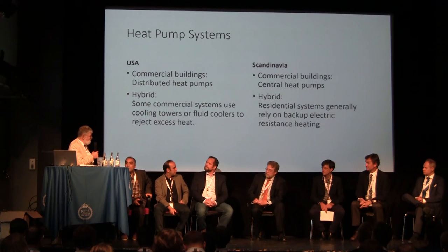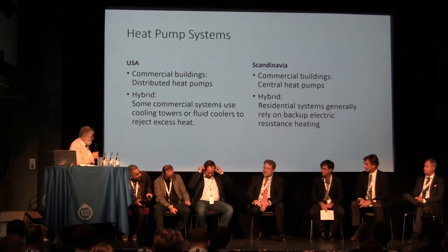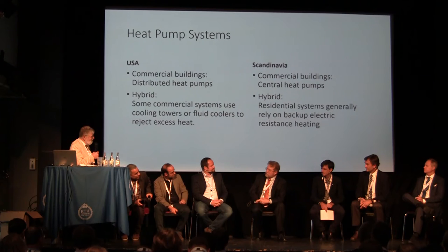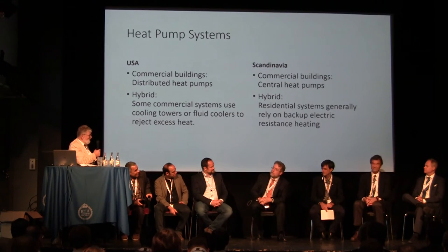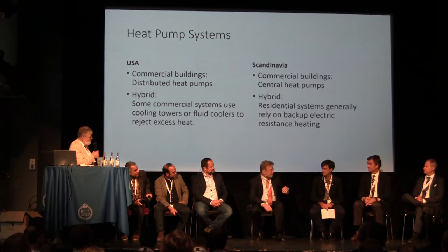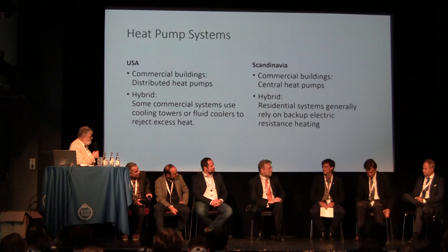Apart from the manufacturers, when we see companies coming in with new heat exchanger products or materials — whether concentric or new polyethylene with flecks of aluminum or graphite — I think the ground heat exchanger is the low-hanging fruit for improvements in our systems right now. Heat pump manufacturers have kept up with developing their technology for many years, but in the US we're still putting polyethylene tubes down holes and grouting with bentonite. New ideas for heat exchangers represent a great opportunity to lower first cost and achieve wider deployment.